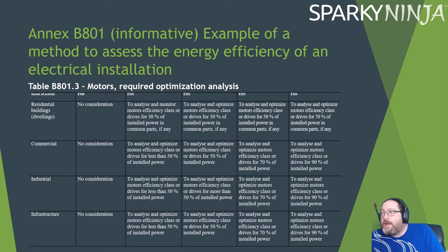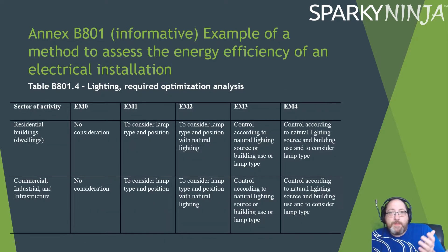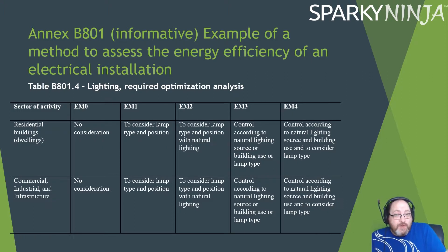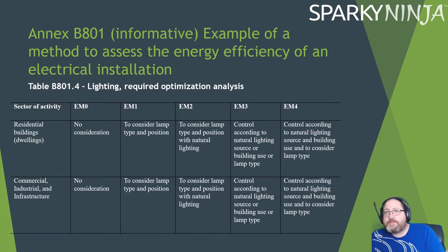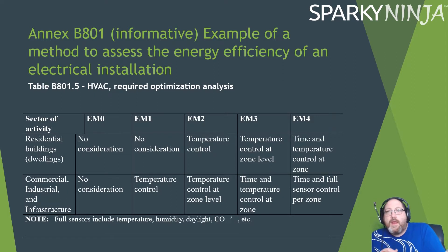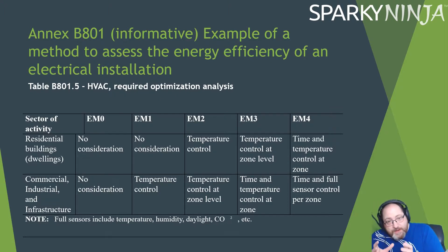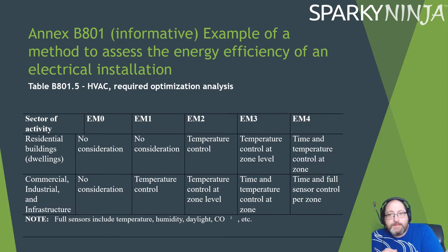For lighting requiring optimization and analysis: no consideration gets zero, and controlling according to natural lighting source, building use, and lamp type gets a four. For HVAC requiring optimization and analysis: no consideration is zero; time and temperature control broken down into independent individual zones gets a four. For industrial and commercial, sensor control per zone is also included at level four.